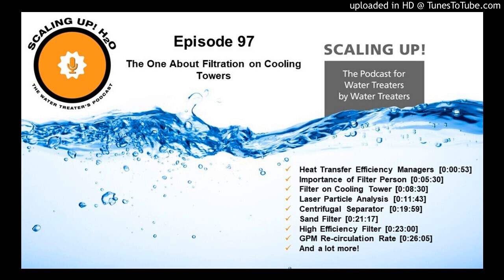Because when you push water straight down through a filter, the spaces in between the sand is where the particulate gets trapped. And if you have too fine a sand, then the top surface of the sand plugs up right away and you keep backwashing all the time. So sand filter manufacturers have had to limit the fineness of their filtration to something that's practical.